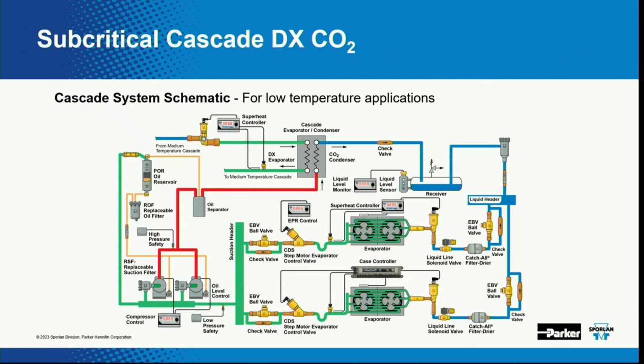All right, guys, listen up. Let's bring it back in. I know you guys are going to want to go over this some more. But the question was, why don't we use a regular condenser up here? Why are we using this brazed plate heat exchanger? The answer is that's just the tool to get the job done. We're passing two fluids across each other through that. A condenser, in the normal sense, has air on the one hand and the refrigerant going through the condenser on the other.